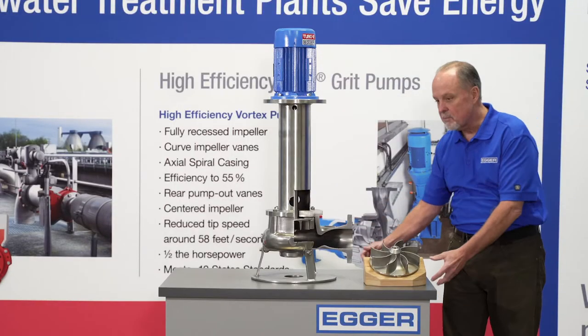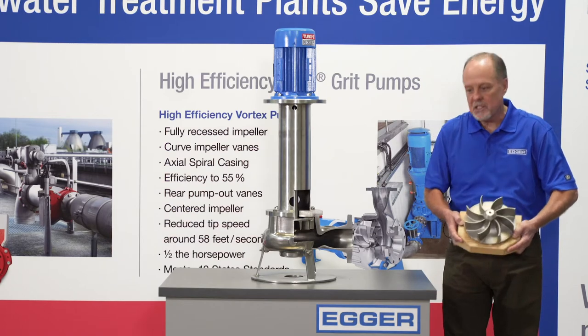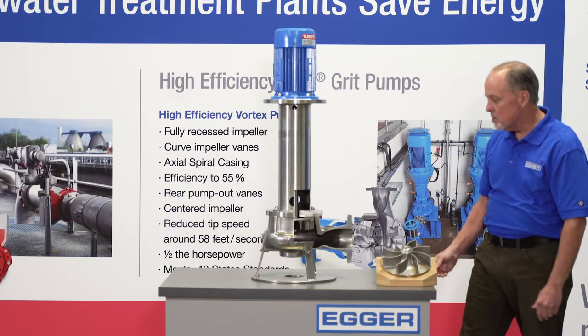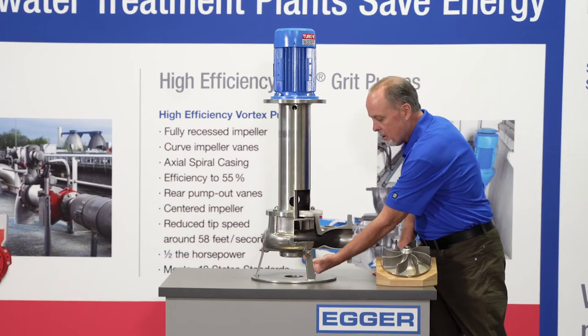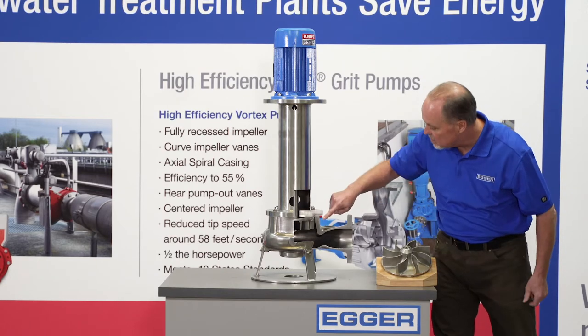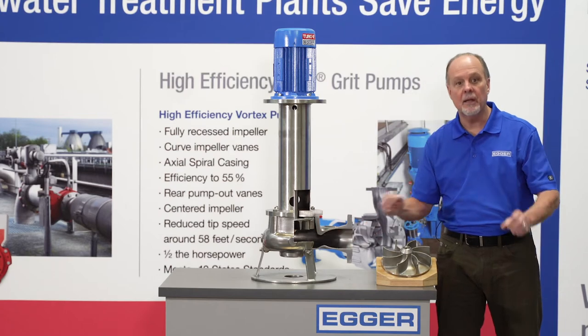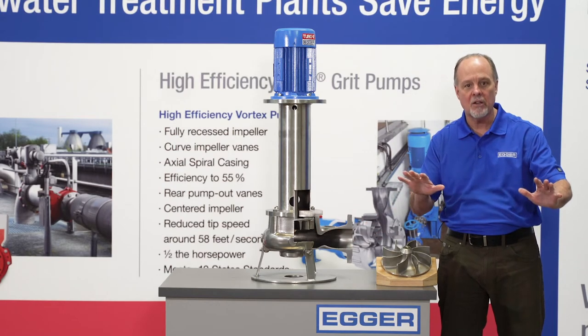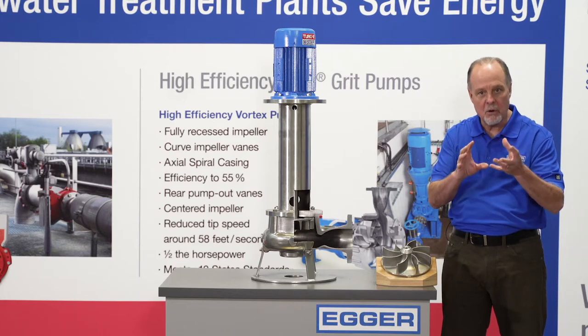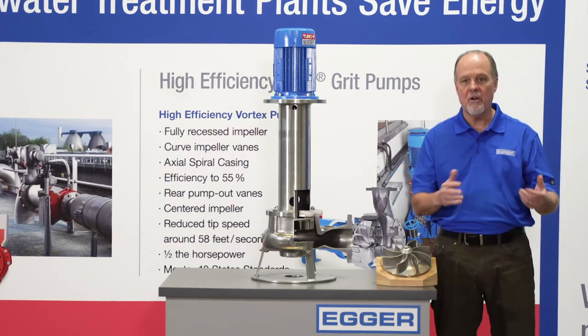This pump utilizes a special impeller with either 8 or 12 vanes that's designed to sit outside of the flow stream in the pump. As you look at this bottom section here and the flow comes in, you see the way this is behind the flow, sitting in its own separate casing, so that the flow comes in and has little or no contact with the sand, the grit, the debris. The flow comes in and gets pumped out very quickly, very efficiently.